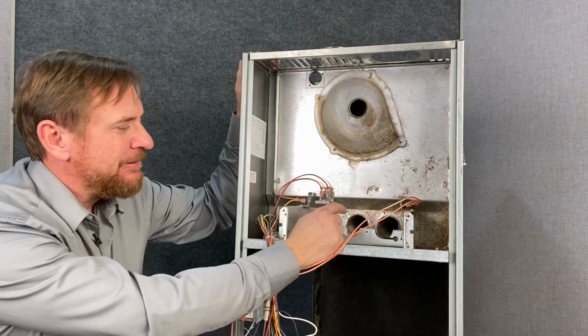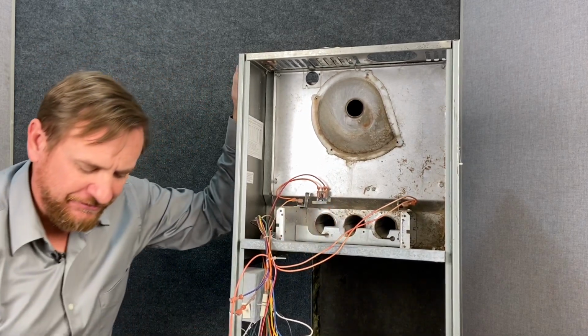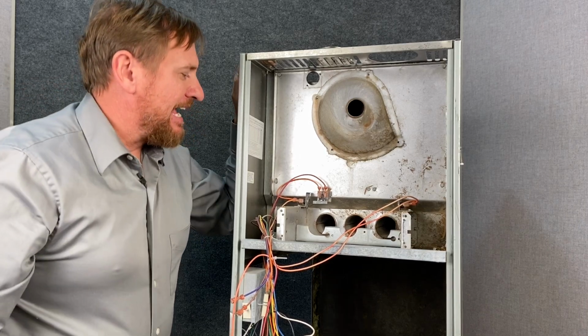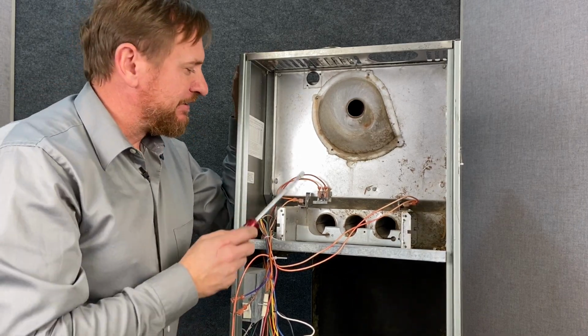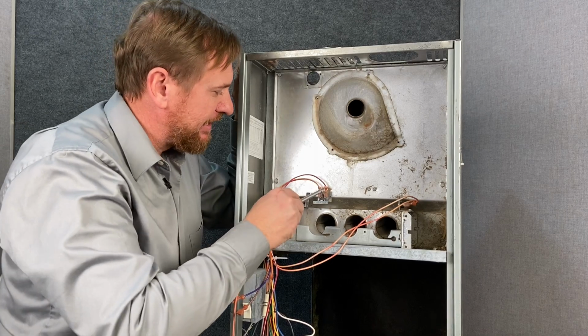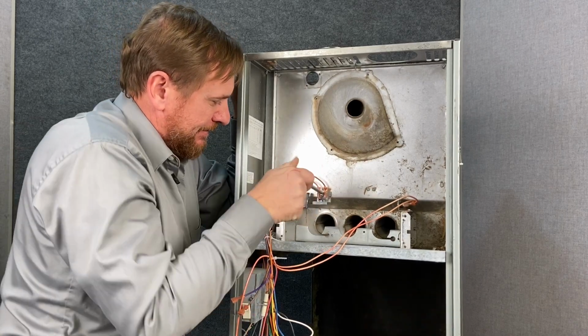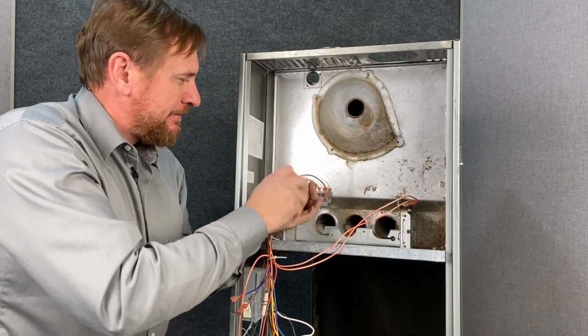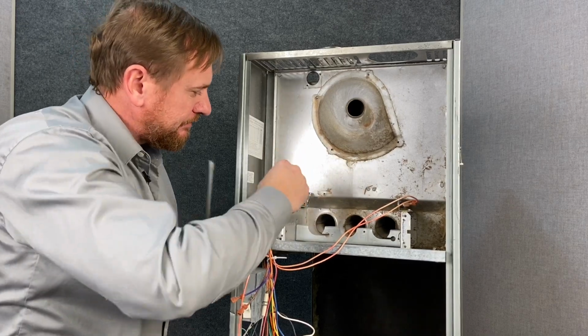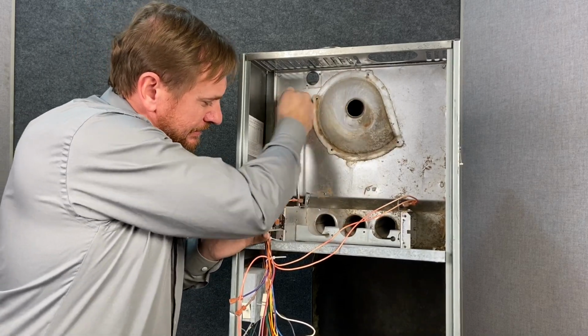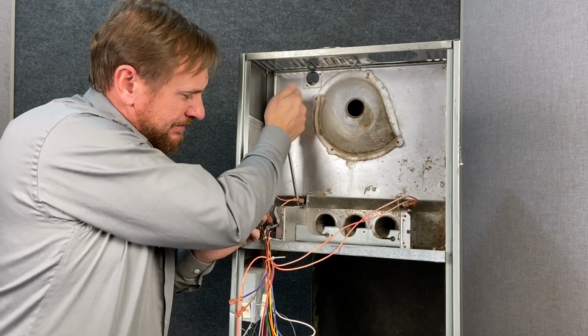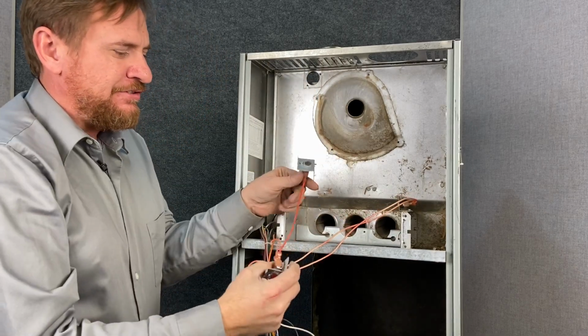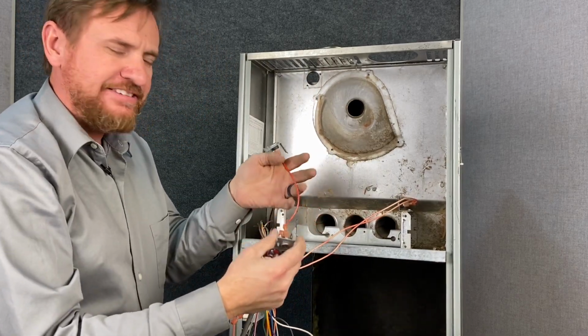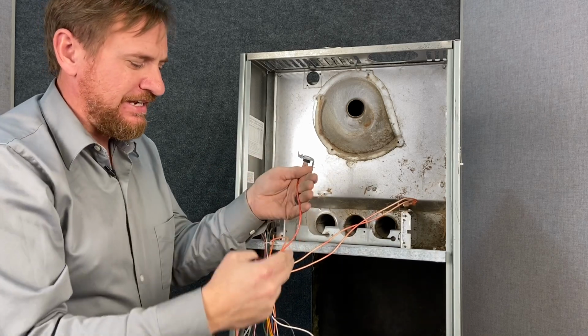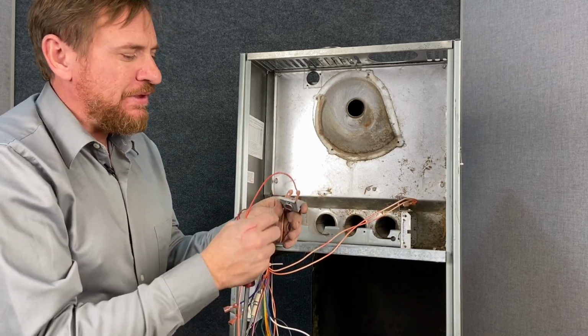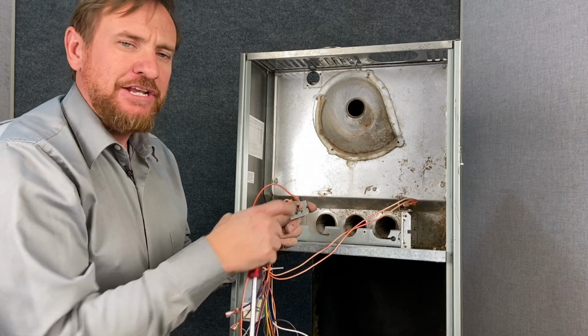These sensors are very important, and these sensors are called flame rollout switches, and they are manual reset for a reason. So we're going to pull one of these off so we can get a better look at it. So here's the flame sensors. They're wired in series, into one, into another, out of the other. But one thing that's really important about this is there's a manual reset.